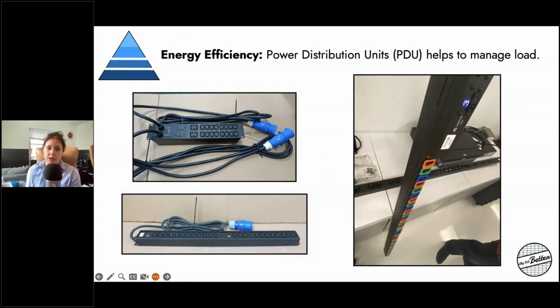Previously I mentioned PDUs, or power distribution units. These are basically like really big power strips, but specifically for data centers and large loads. They can be so-called dumb PDUs, like the ones on the left, or smart PDUs, like the ones on the right. This helps you control demand and power in the space. If you have smart PDUs, you're not just plugging into an outlet - you're actually able to log in and manage your power for your facility.